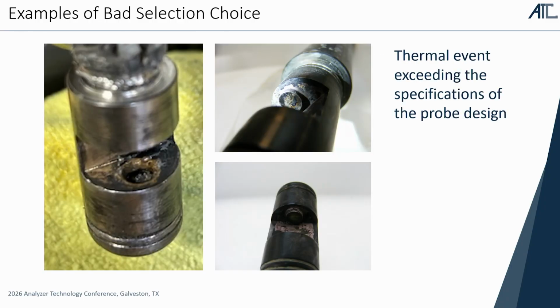Here's a process event. Somebody said, oh, my process doesn't get very, very hot. Well, they didn't think about the thermal soak and everything else that was going to be happening, and they burned up the probe, right? The stainless steel there got blued. We actually debrazed the optical window, the metal seal there on the bottom in this big left photo. I don't know where the window went. It went clinkety clink clink down. It's probably in somebody's valve.